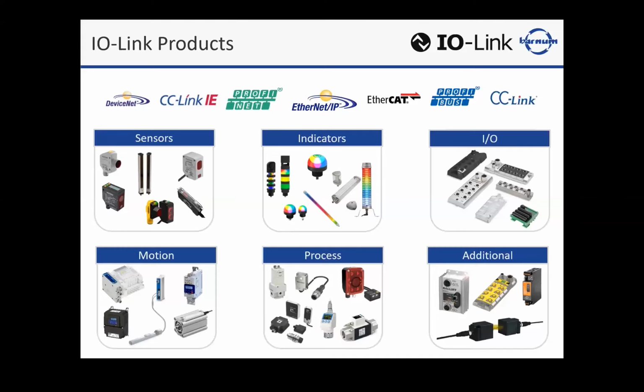But besides that, describe what we got in motion. So motion up to this point has typically been pneumatic motion or valve control. We're using a valve manifold communication module. Typically in the past, it's been, let's say, Ethernet or Profinet. And now we can get those directly for IO-Link, so we can control those directly from an IO-Link master.